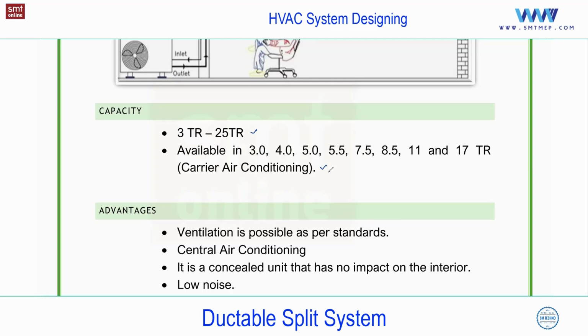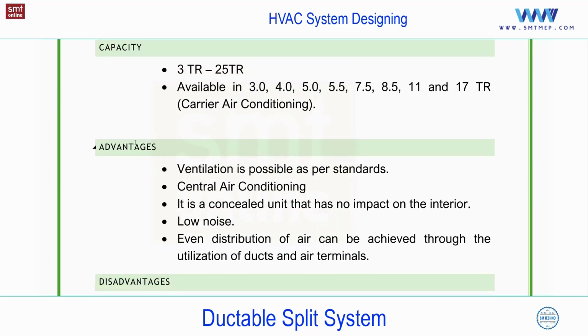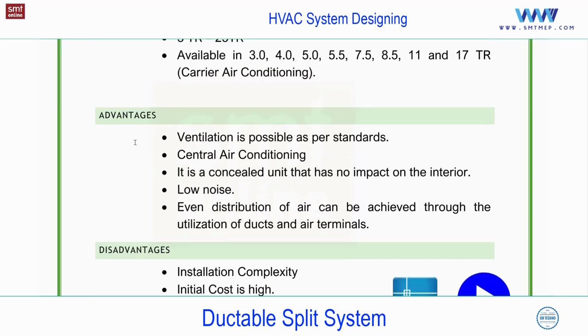Now you see the capacity I explained, 3 TR to 25 TR in general. Here one example is given as per Carrier. In Carrier, you will find up to 17 TR with different configurations like 3, 4, 5, 5.5, etc. In each, you will find two models with a different RPM and a different CFM. So depending on the make, you will find multiple models with the same capacity also, as per the size of the unit, which suits the site condition, etc.